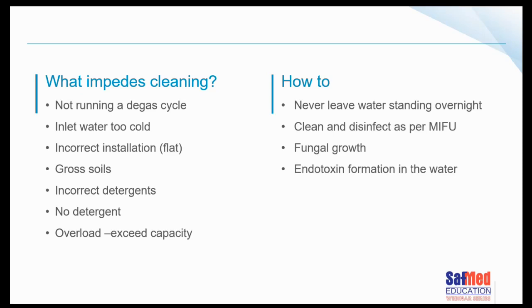A lot of our washers are more equipped to warm water from cold, perhaps, whereas our washer disinfectors are less likely to be able to do that. So the incoming water needs to be at the right temperature. As I said, making sure it's installed flat, otherwise the water sensors are going to alarm the whole time. Gross soils on instruments is also going to be problematic, so you may need to pre-rinse your instruments before putting them in the ultrasonic cleaner.